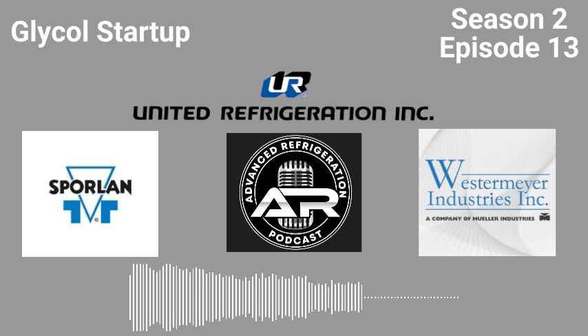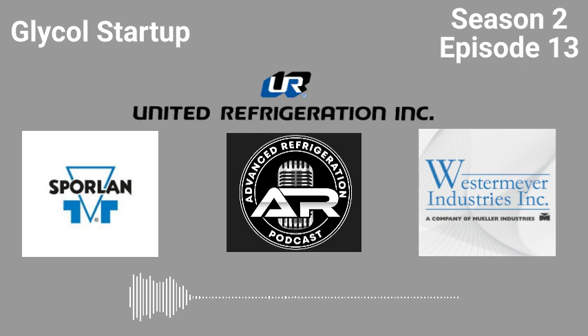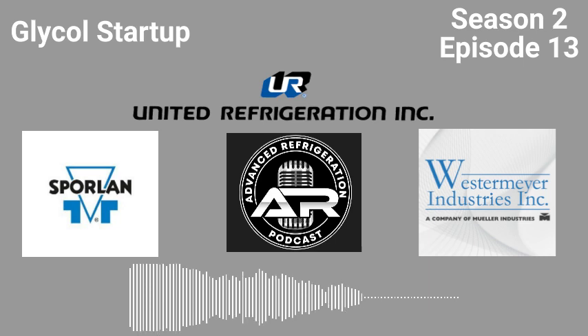Generally, what I'll do is I'll just watch it. You'd be surprised how fast it'll drop the glycol when you're charging it. So just keep an eye on it and make sure you're not going below your freezestats. If your freezestats are set, check them. Most of the time they're set for 13 degrees. Make sure you're not going below 13 degrees. And if you are, stop charging and shut the rack down, let everything warm up, let the refrigerant pressure come up so the SST comes up, and then the chillers will warm up a little bit. You don't want to frost over a plate frame heat exchanger. I mean, you want to make sure everything's good.